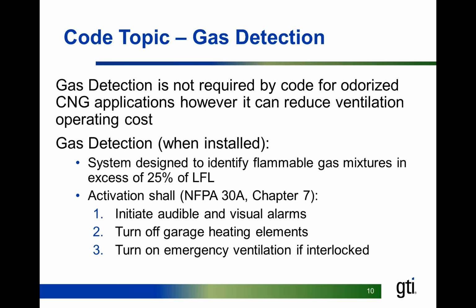Gas detection, as I mentioned in a previous slide, is not required by code, especially for CNG, which is typically odorized. But where it does come into play often is that if you have it tied into the ventilation system, you don't need to have a continuously running ventilation HVAC. And as you can imagine, and as this winter has proved, it could be a very high operating cost if you had to continually run your HVAC in cold weather, as this entire region has seen plenty of.